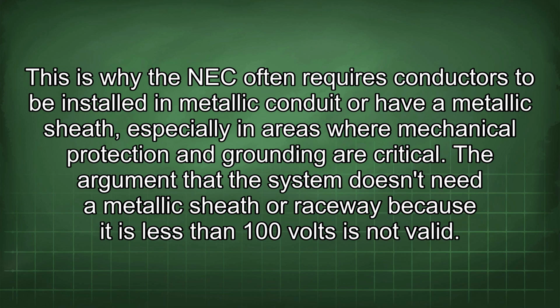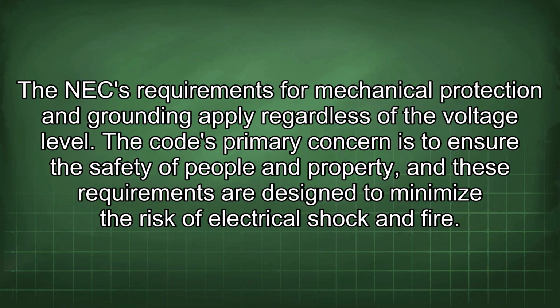The argument that the system doesn't need a metallic sheath or raceway because it is less than 100 volts is not valid. The NEC requirements for mechanical protection and grounding apply regardless of the voltage level. The code's primary concern is to ensure the safety of people and property, and these requirements are designed to minimize the risk of electrical shock and fire.